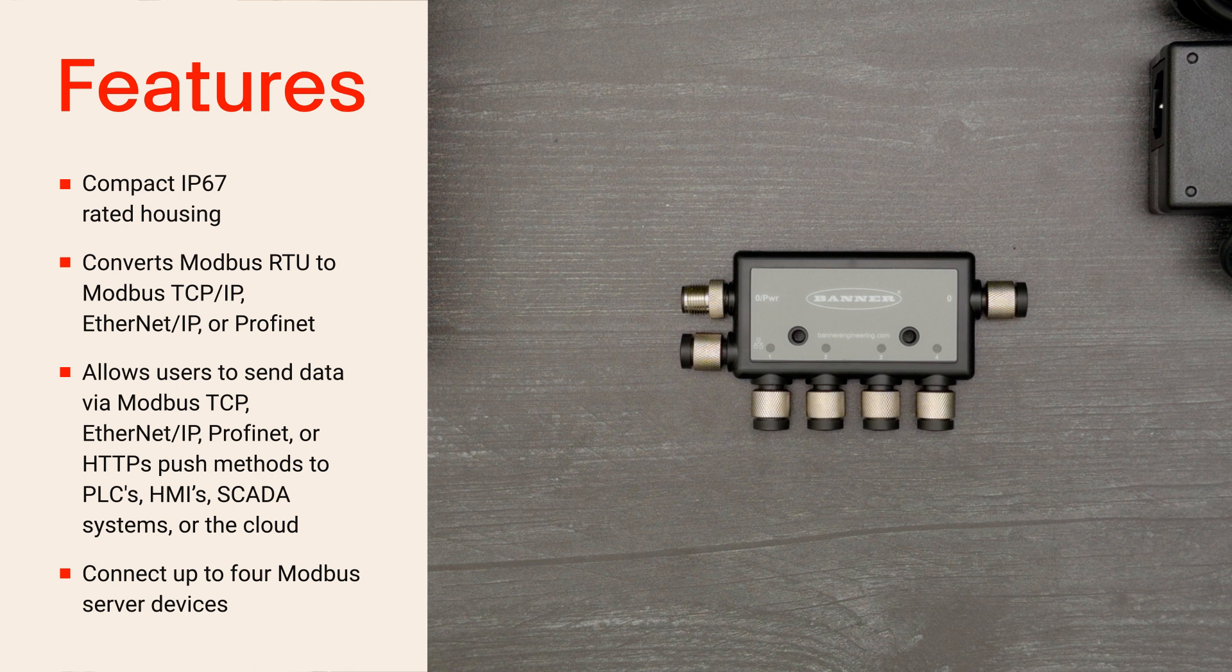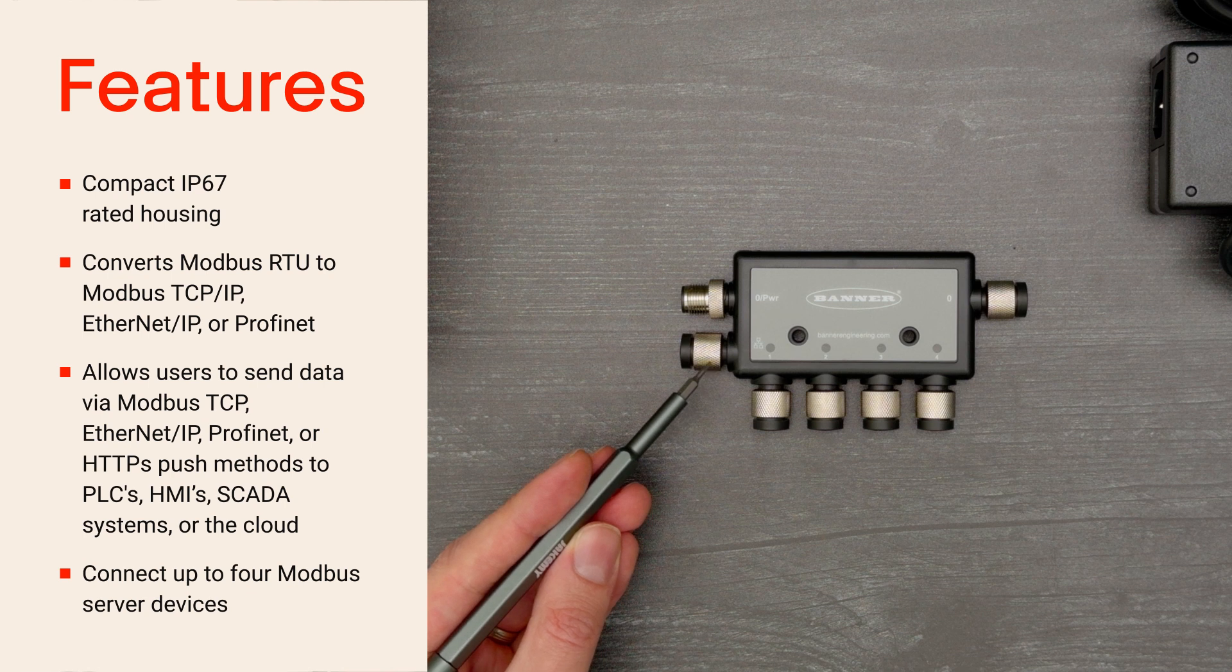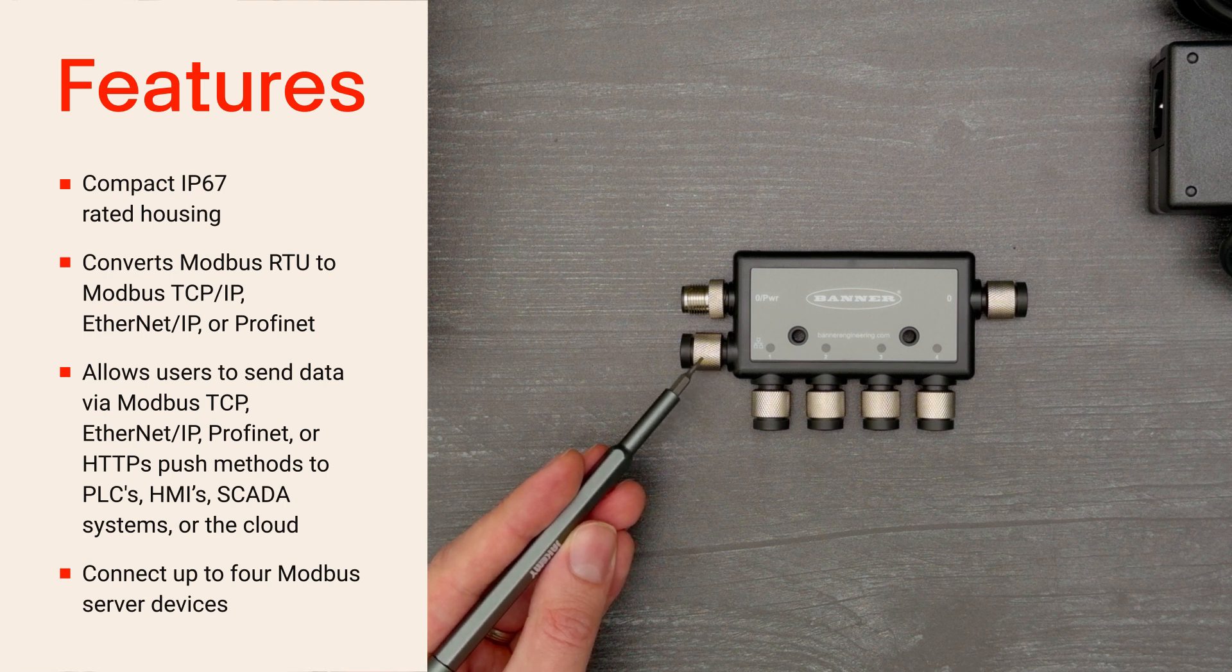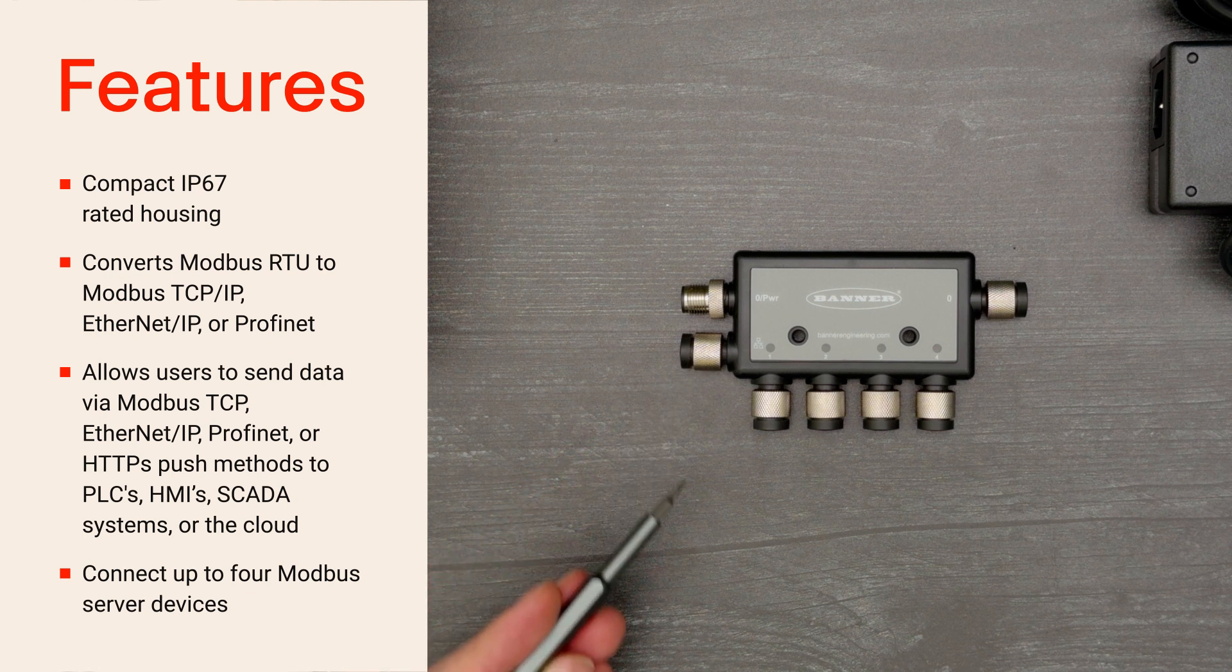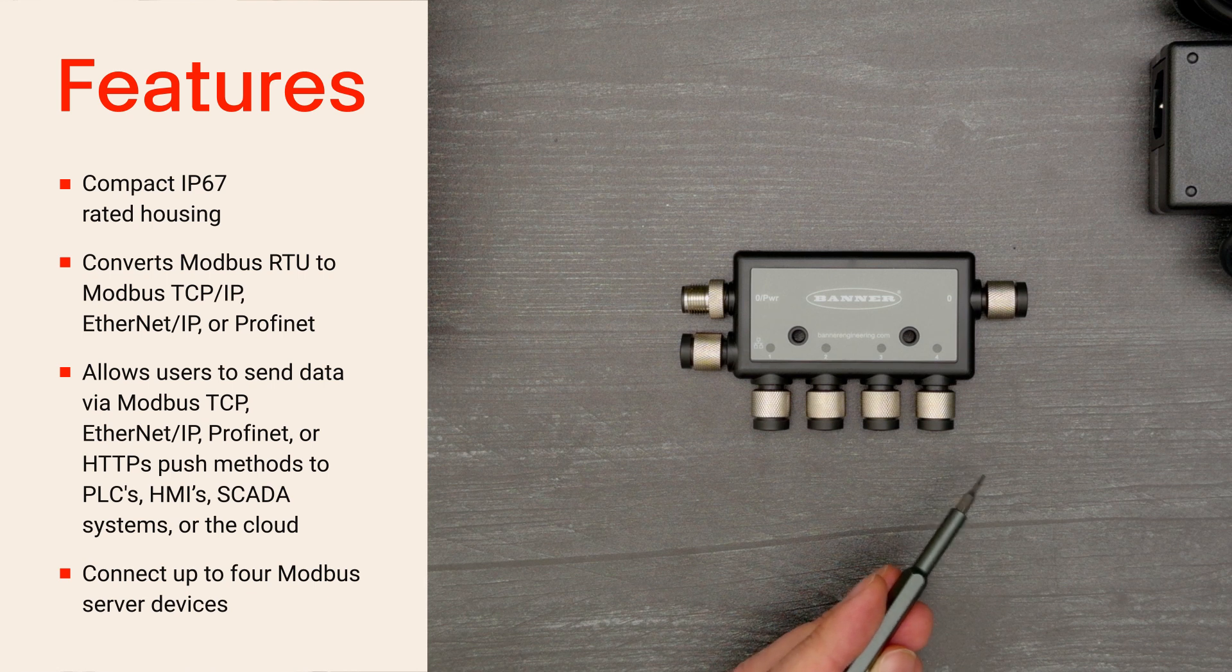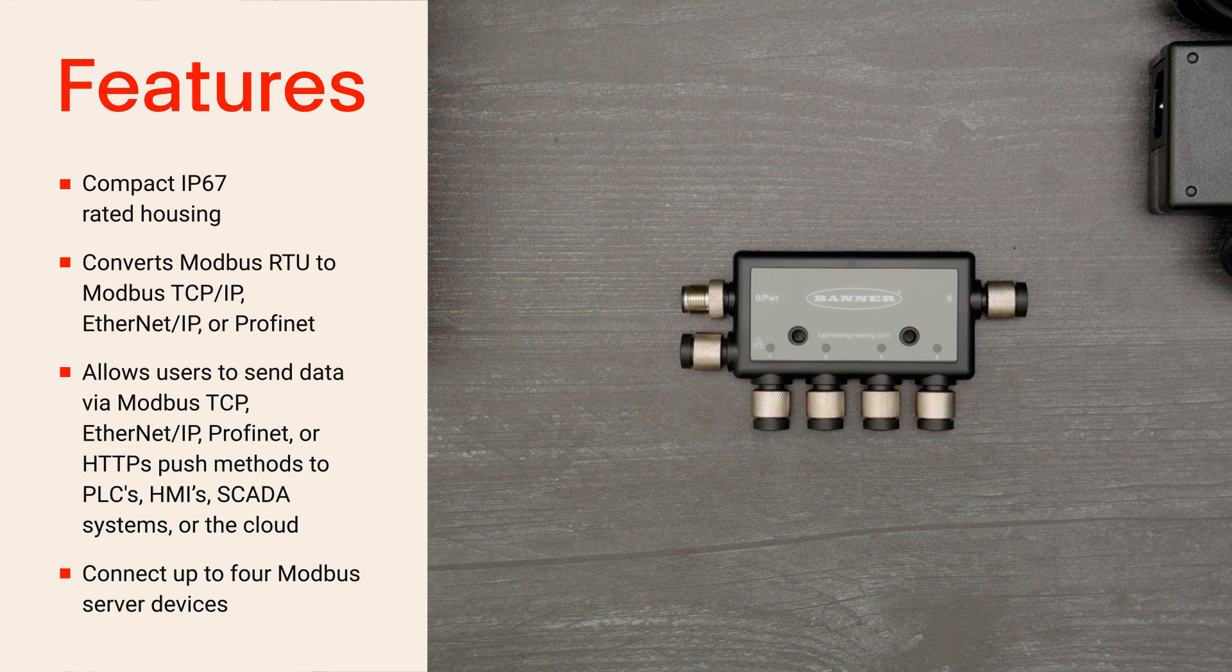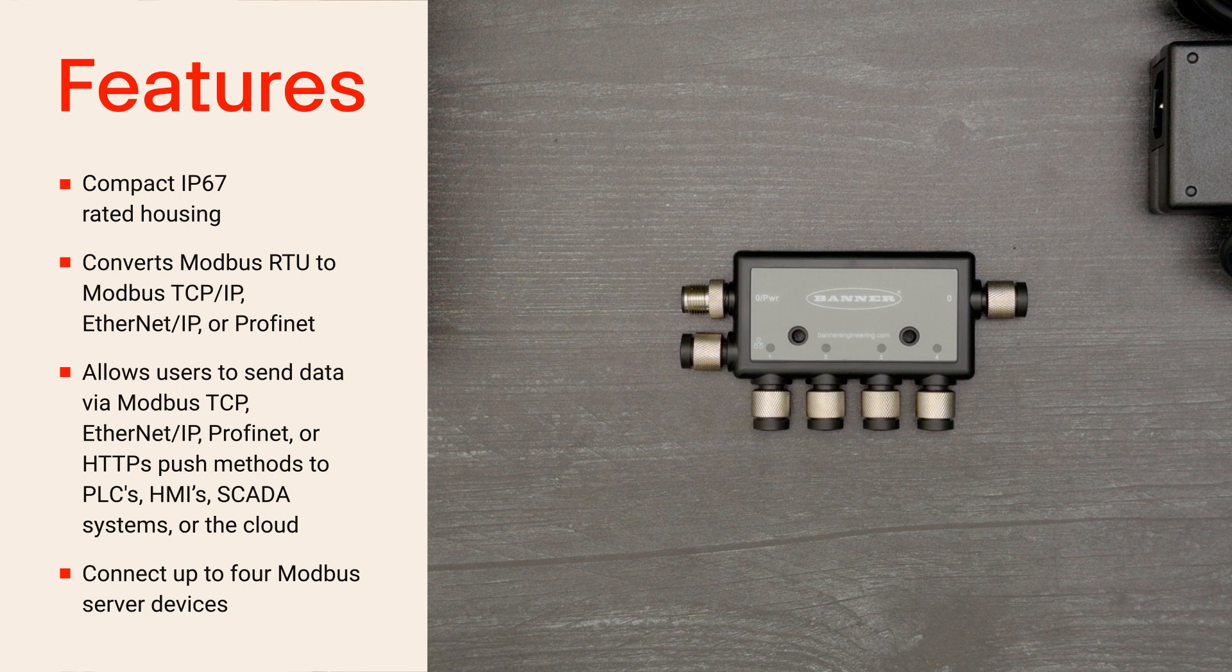It includes a 100 megabit per second Ethernet port and four independent Modbus client ports that enable simultaneous communication with up to four chains of Modbus server devices. Each chain can contain multiple Modbus server devices when daisy-chained together.